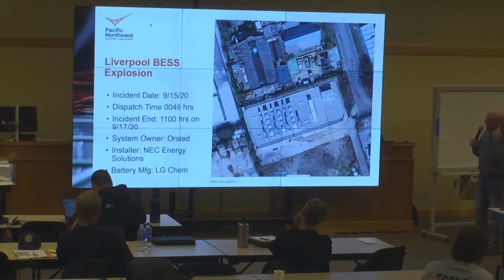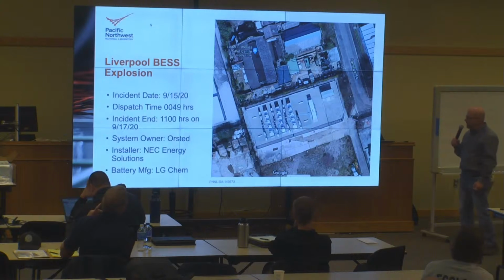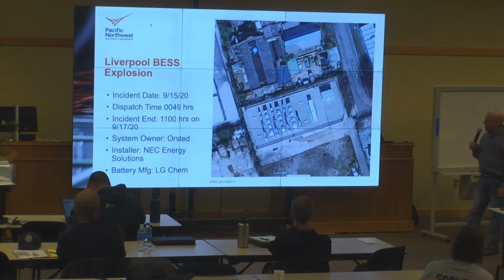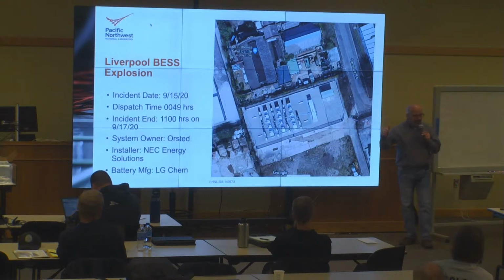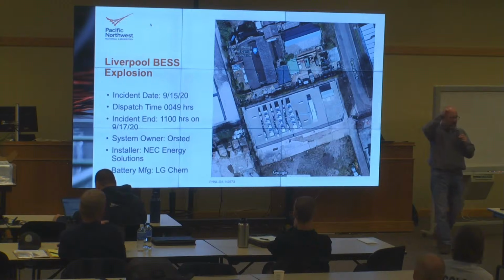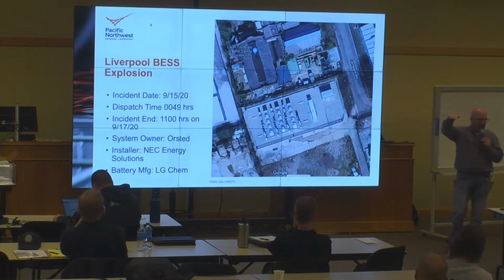Now, I don't know how many of you have heard about this one, but this was a utility installation in the UK, back in 2020, in September, there was an explosion around midnight. This system is owned by an operator in Denmark, and they were using it for frequency regulation. In other words, they were just injecting power very quickly to keep the frequency of the voltage right at the desired hertz.